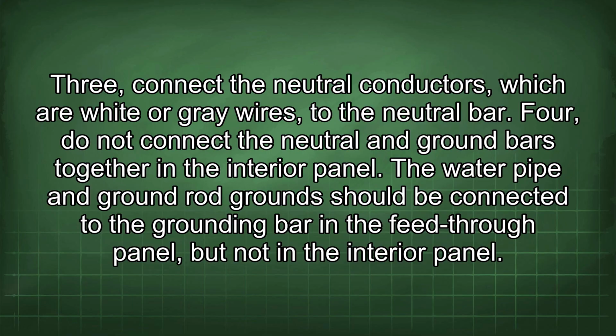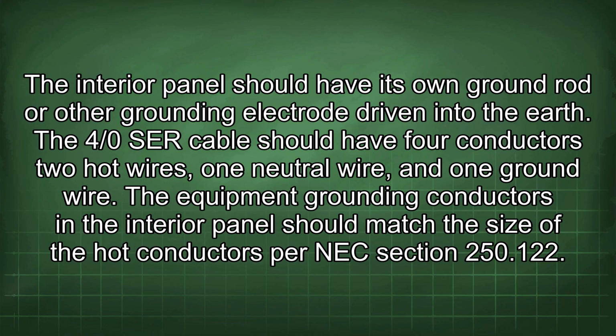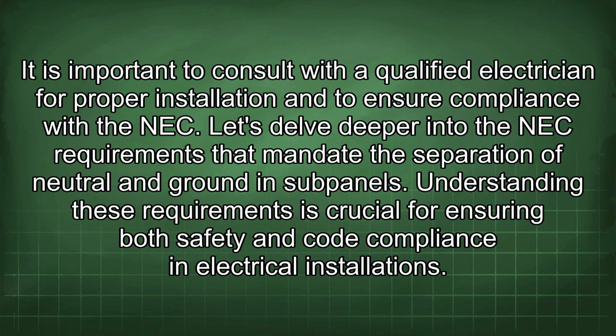The water pipe and ground rod ground should be connected to the grounding bar in the feed-through panel, but not in the interior panel. The interior panel should have its own ground rod or other grounding electrode driven into the earth. The 4/0 SER cable should have 4 conductors: 2 hot wires, 1 neutral wire, and 1 ground wire. The equipment grounding conductors in the interior panel should match the size of the hot conductors per NEC section 250.122. It is important to consult with a qualified electrician for proper installation and to ensure compliance with the NEC.